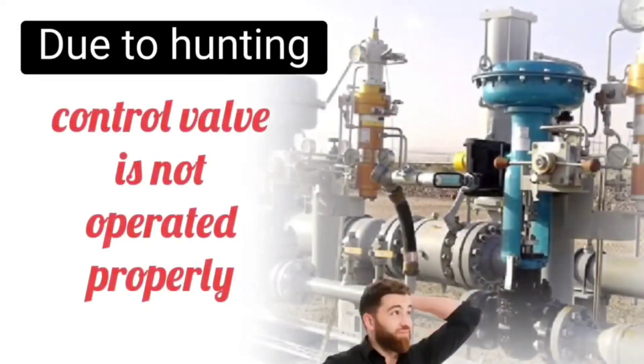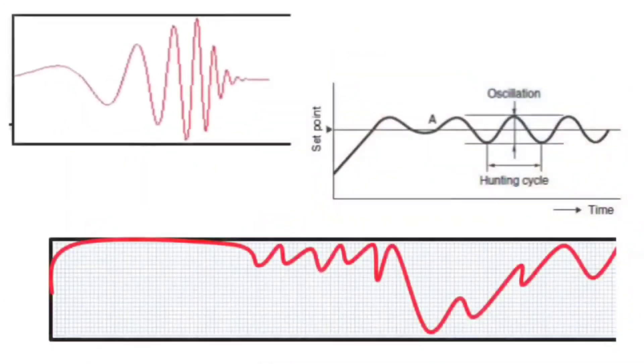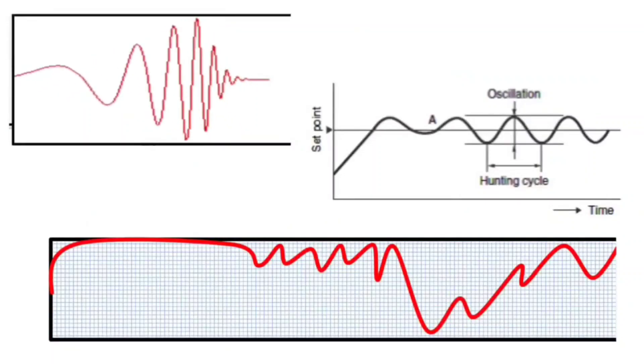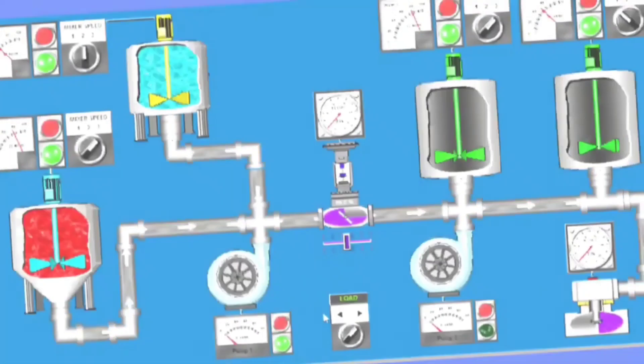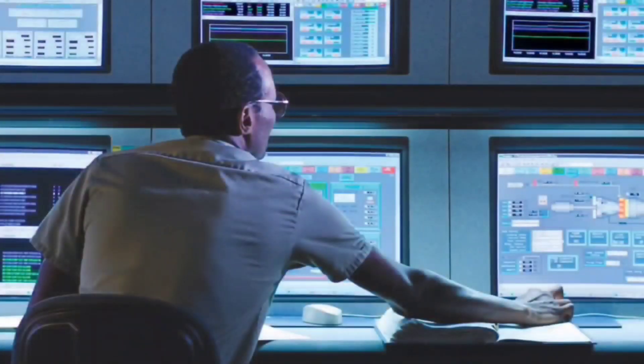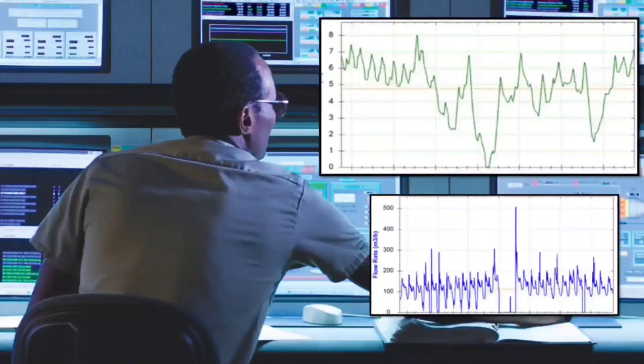Due to control valve hunting, the control valve does not operate properly, and the process variable changes randomly, which means the process may be disturbed. If you see the trends on SCADA at the time of hunting, these types of erratic trends will be visible. By SCADA, you can easily see how long the hunting has been going on.